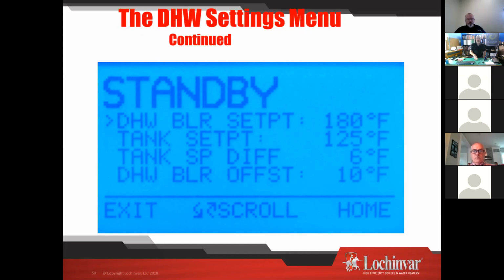Now, it's not a one size fits all. There are going to be those days that, hey, maybe this indirect's a little bit undersized, so I've got to run my boiler a little hotter to recover it. But as a general rule of thumb, 20 degrees above your tank set point, and you're going to heat your domestic hot water just fine. Again, I like to use my house as an example. I'm at 124 degrees right now, my tank set point, and I run 146 degrees for my boiler. If you watch my boiler, it's almost always condensing. Even in a domestic hot water call, the boiler's condensing just because of those low temperatures.